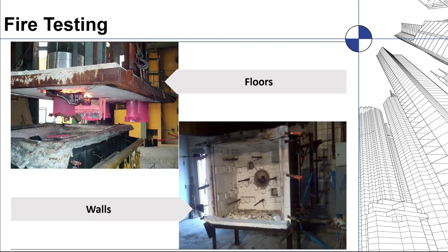One is a test for flame. That would be to make sure that flame on the hot side, where the furnace is, is never visible on the cold side, which is where, if you were viewing this fire test, you would see nothing but a gypsum wall, and back behind that would be all the heat in the furnace and all that cooking on the back side of it. They want to make sure that no flame is ever visible on the cold side of the furnace. That would be a failure.